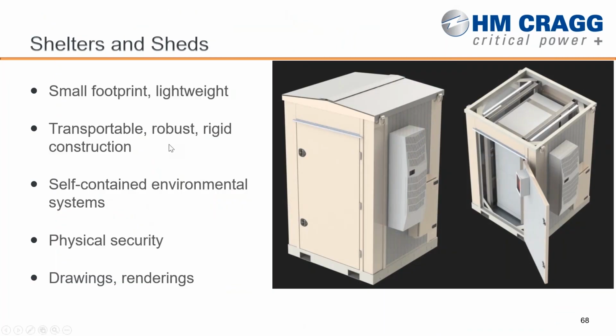The last thing I want to talk about is that we've continued to expand our capability and now have some partners that can fabricate shelters and sheds for us. We've talked about limitations of true enclosures, a lot having to do with heat containment and hydrogen gassing, but the biggest piece is really about airflow, especially for a larger system, say bigger than a 9355, a 93E, or a 93 PM, and certainly if it has an external battery cabinet. There are a couple of ways to tackle that. One is multiple enclosures, one with the UPS and a second with nothing but the batteries, joined in the field or connected with custom cable assemblies for the positive and negative DC cabling plus communications between the UPS and battery cabinet. Another way is to use a full-blown shelter or shed.